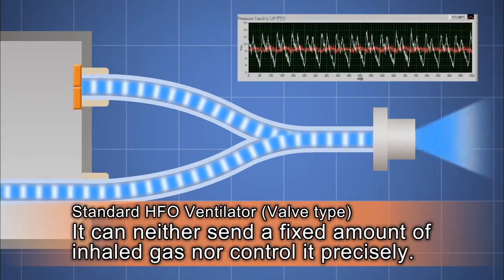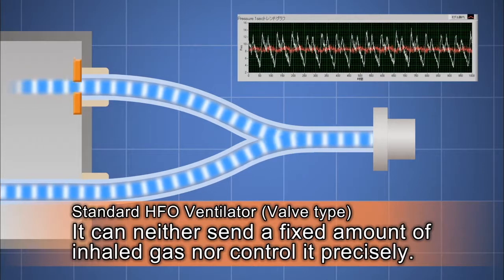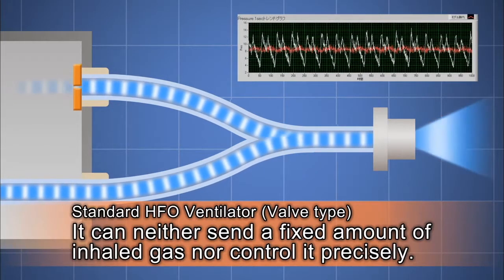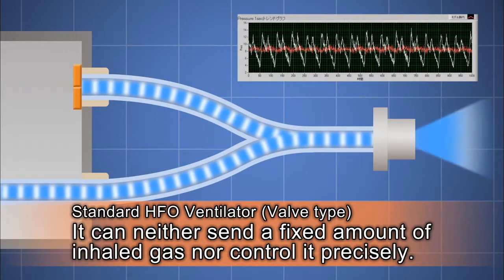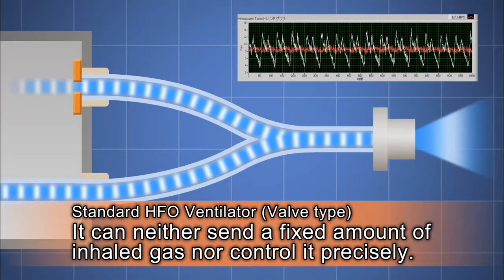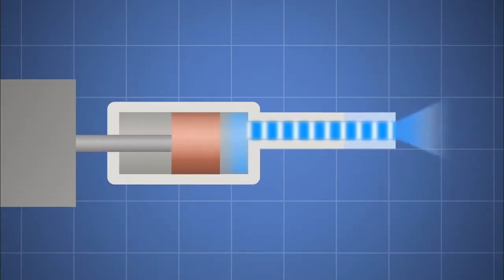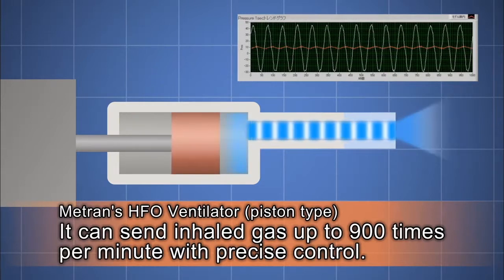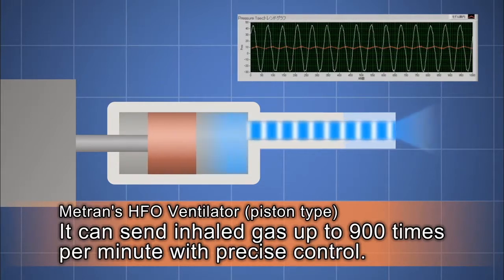Standard HFO ventilators send gas compressed by a valve. That type of ventilator doesn't provide uniform gas volume, nor can they be precisely controlled. In contrast, Metran's ventilators are able to precisely control gas volume, thanks to a linear motor-driven piston.